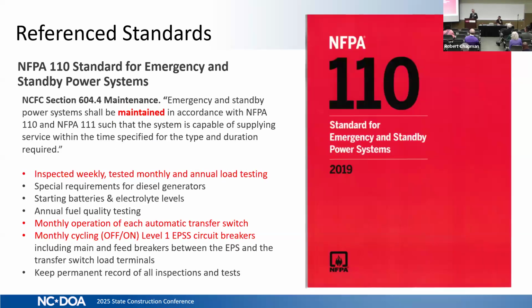Another reference standard that's in the building code is NFPA 110. This is the standard for emergency and standby power systems. I call your attention to the red highlighted items. Often what we see for building owners is that once the generator is installed, they fail to maintain the generator in terms of the testing that is required monthly by this reference standard. And when they do the testing, they don't load the generator up. They just turn the generator on, run it for 30 minutes and turn it off.